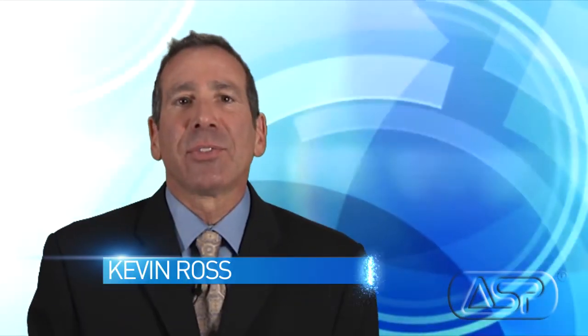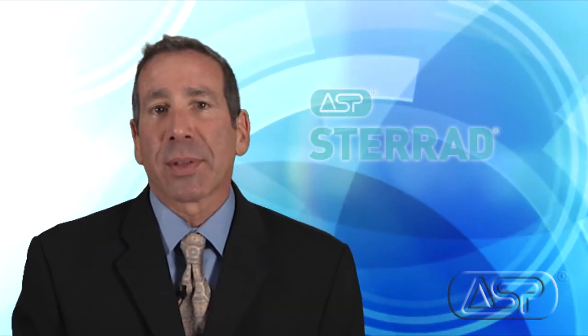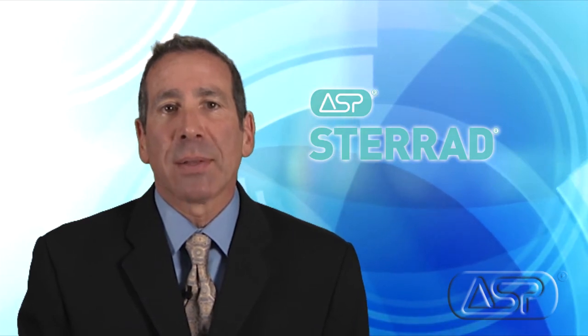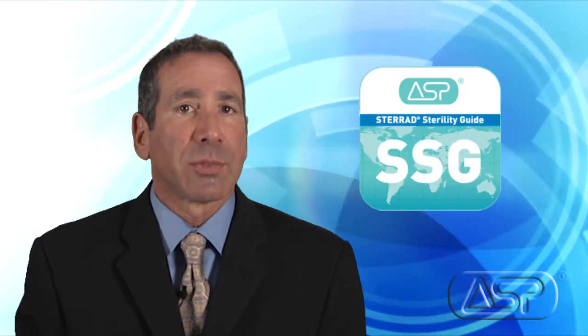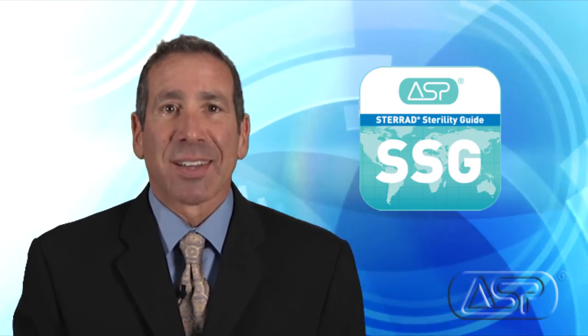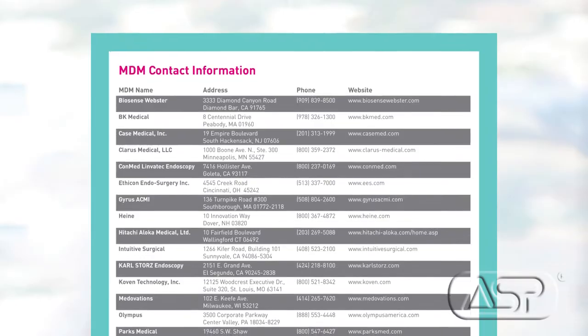Thank you, Barbara. In this dynamic environment and increasing focus on IFU compliance, we're pleased to report that STERRAD systems are currently listed in IFUs by many device manufacturers for terminal sterilization. At ASP, we work closely with many medical device companies to make sure we maintain the most current IFUs for instruments listed in our online reference tool, the STERRAD Sterility Guide, also known as the SSG. Every device listed in the SSG is backed by an acknowledgement from the device manufacturer in their labeling or instructions for use.